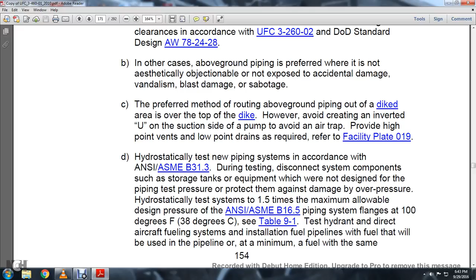See Table 9.1. For testing hydrant direct aircraft fueling system installation fuel pipelines, the fuel to be used is the fuel with the minimum specification flash point that will be used when the piping is in service. The temperature of the fuel and the ambient temperature shall be at least 20 degrees Fahrenheit below its flash point during the testing. Testing with water requires service headquarters approval.